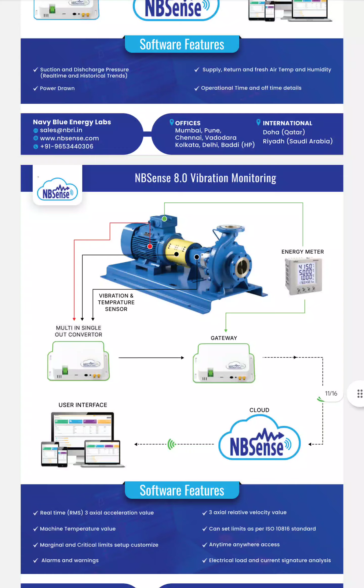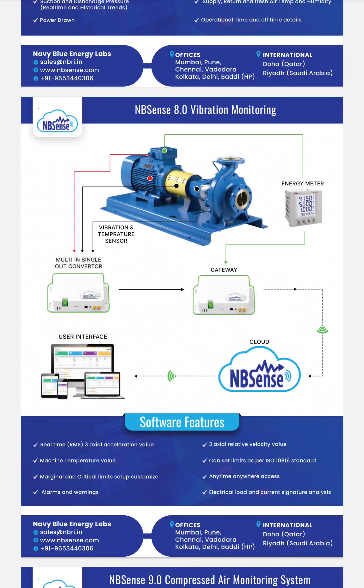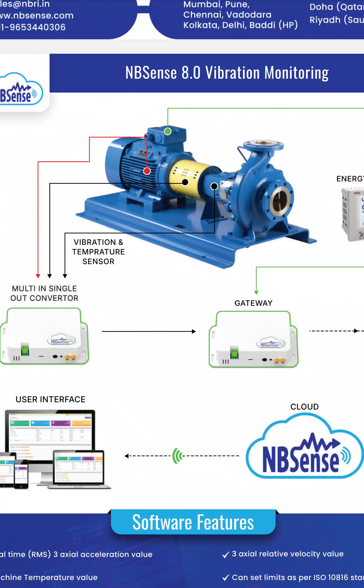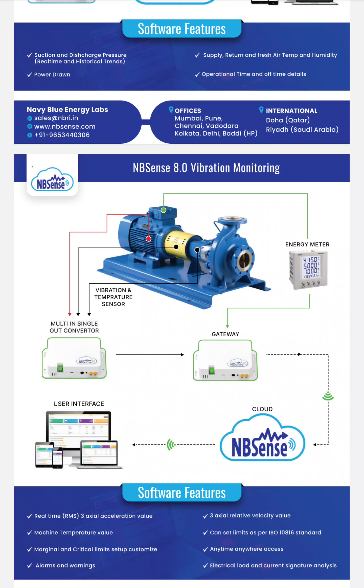The next solution is vibration monitoring, which comes under condition monitoring in the category of predictive maintenance. In any rotating machinery, before failure, the machinery starts to give abnormal signatures of vibration, temperature and current. Our system closely monitors these parameters by putting vibration sensors on the body of motors or drives, and temperature sensors on the motors and drives. With data analysis, this can interpret potential failure or abnormalities in the system, giving early prediction so you can avoid unpredicted downtime. This is possible in our vibration monitoring system.